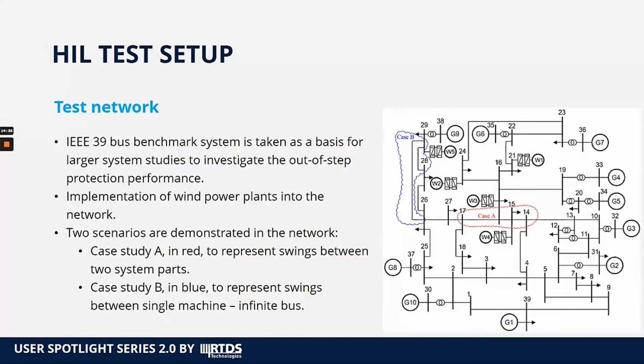As for the testing network used for the hardware-in-the-loop simulations, the IEEE 39 bus benchmark system was taken as a base, and to this we added wind power plants in order to investigate the protection's performance in different network scenarios. 2 testing cases are chosen to show the algorithm's performance in different network conditions. Case study A, noted in red, represents power swings between 2 larger parts of the network, and case study B, shown in blue, represents a single machine to infinite bus type of scenario.